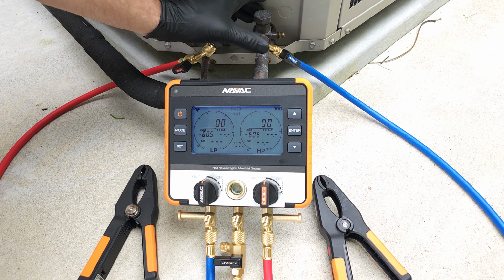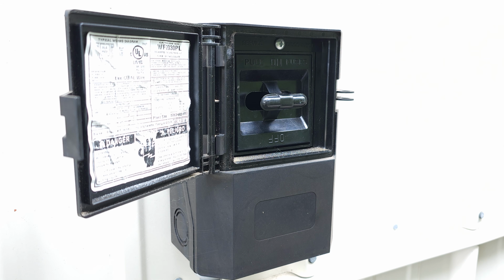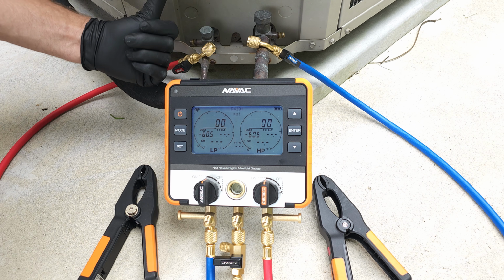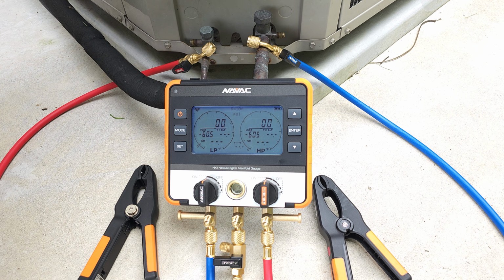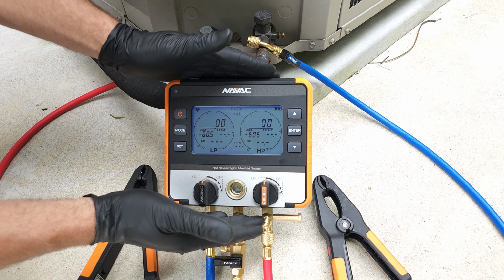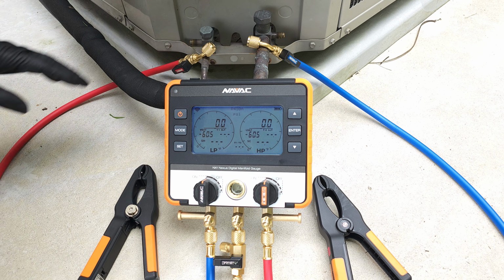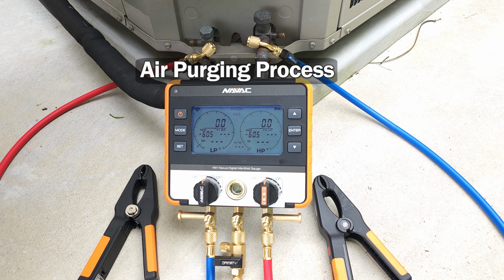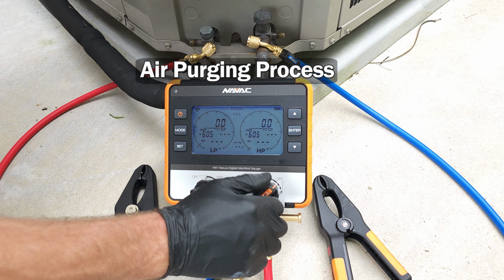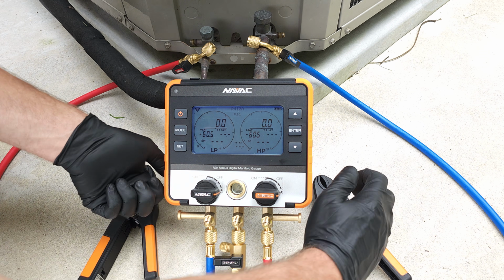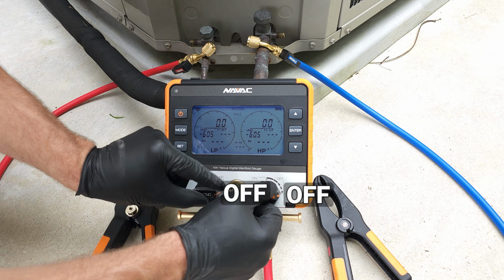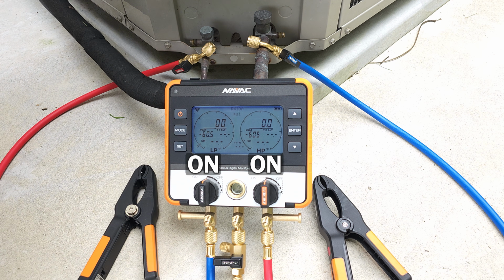We've allowed this suction line to thaw out by turning this outdoor unit off while we let the indoor unit continue to run its fan motor. And so we're getting ready to connect our digital manifold set to this system, and we're going to do the air purging process. You can see on a manifold set, usually you'll have handles or valves here. We're in the off position. You're going to want to turn them to the on position.